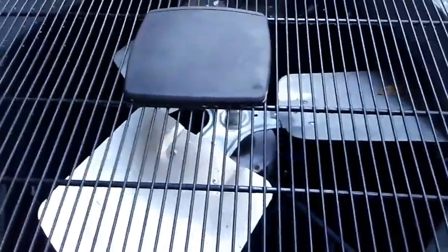We are looking at a Goodman unit that has some issues — the bracket is broken, the fan is tilted, and you can see it rub right there. I don't know if we got a hole in there but it's awful close. I don't know if this is ice storm related or not, but I might take this apart and shut the power to the unit. I have one of the manifold probes on there and as you can see there is no pressure in the system at all.